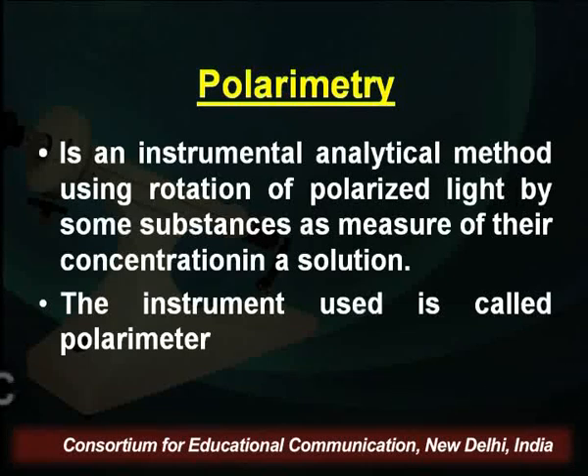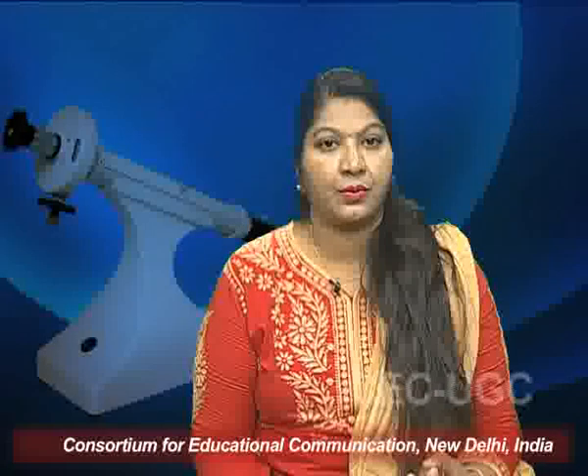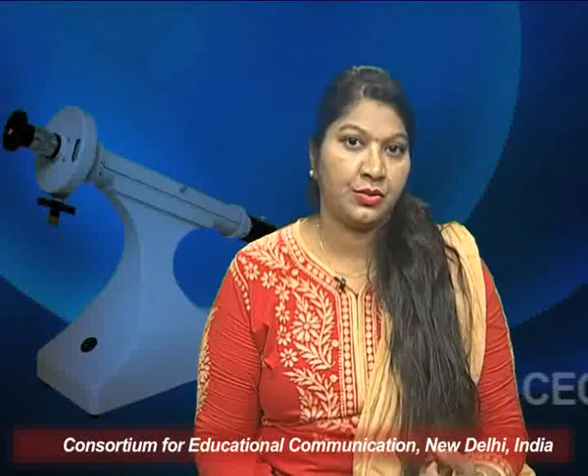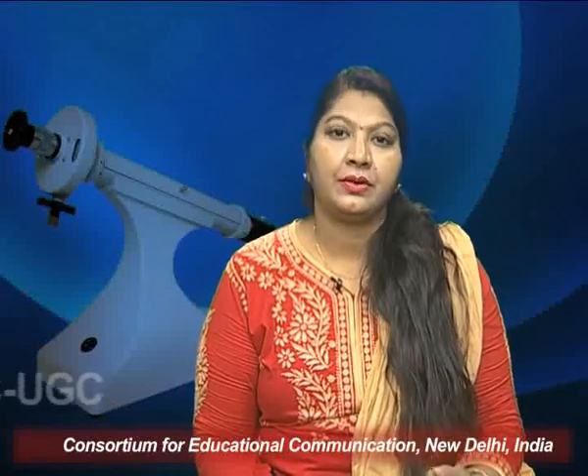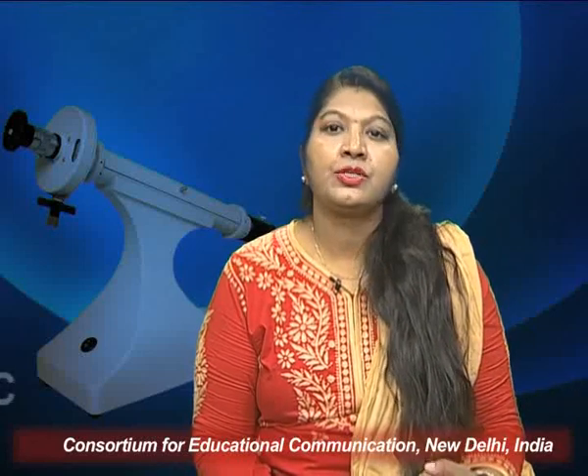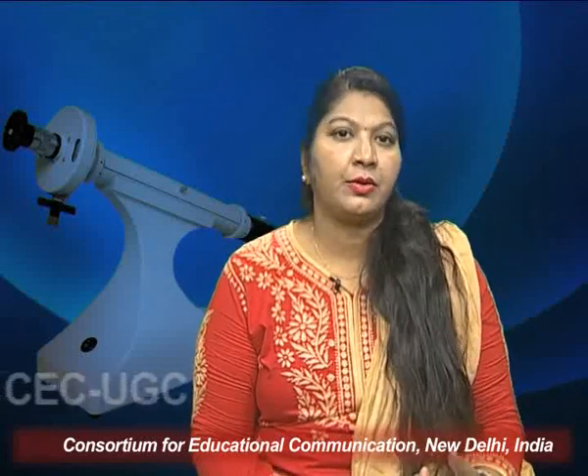It means concentration plays an important part, how concentrated the solution is that we are using to get the output. So this polarimeter instrument is used to find out the rotation of polarization of light by a particular substance which is optically active, and we can find out the concentration of that solution. That instrument is called the polarimeter.